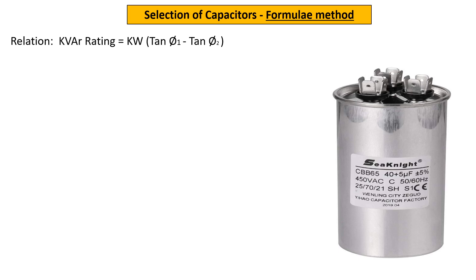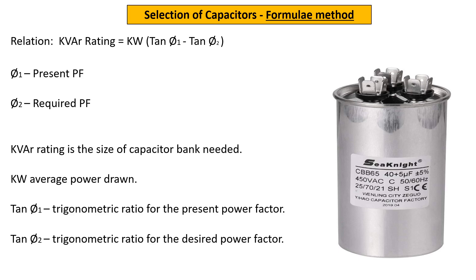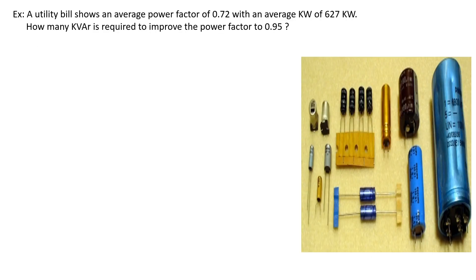In this formula method, the capacitor rating is in kVAR. For this method, the present and required power factor along with load in kilowatt need to be known. The present power factor is 0.72 and the desired power factor is 0.95. So, how much kVAR do we need to add?